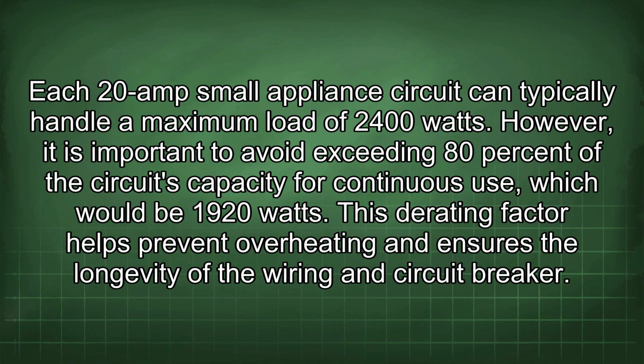Each 20 amp small appliance circuit can typically handle a maximum load of 2400 watts. However, it is important to avoid exceeding 80% of the circuit's capacity for continuous use, which would be 1920 watts. This derating factor helps prevent overheating and ensures the longevity of the wiring and circuit breaker.